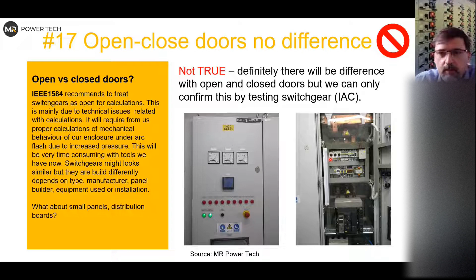That's purely because we would have to go through all the FEA calculations, which would be extremely expensive to do for one panel. You need to take into account whether it is fully closed, because if you have 3 locks and it's closed with 2 locks, it makes a difference. Sometimes it's not closed at all, but most of the time on a low voltage system, when you work with it and start to open things, yes, there will be a difference, but eventually the worst case is the open door. So we generally treat open and closed as open. And of course, you have all the small panels and distribution boards, where, if I go through the slides, you see the flipping doors, closed, not closed, locked, not locked. It makes a big difference. And they are plastic or metal.